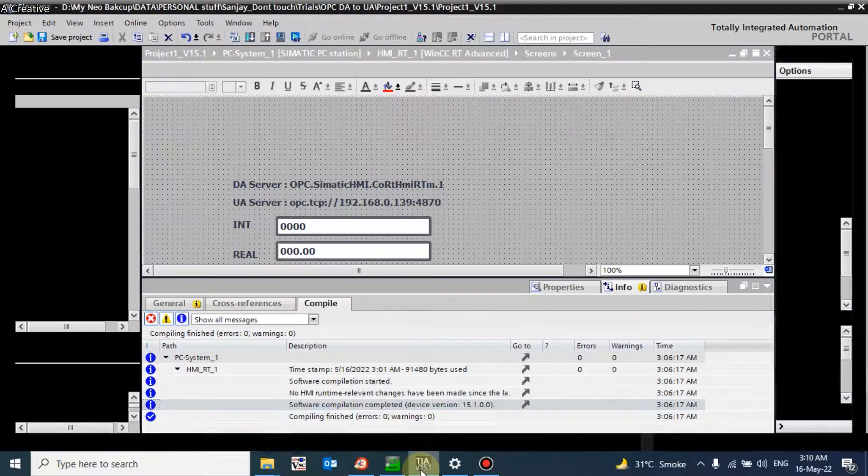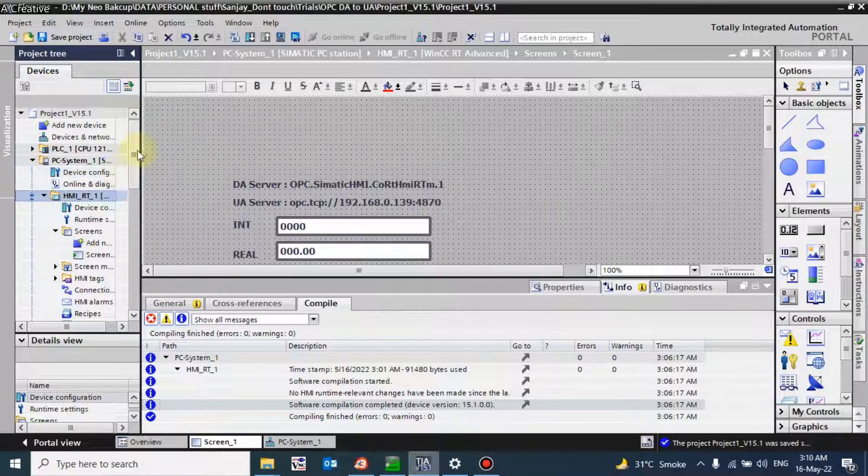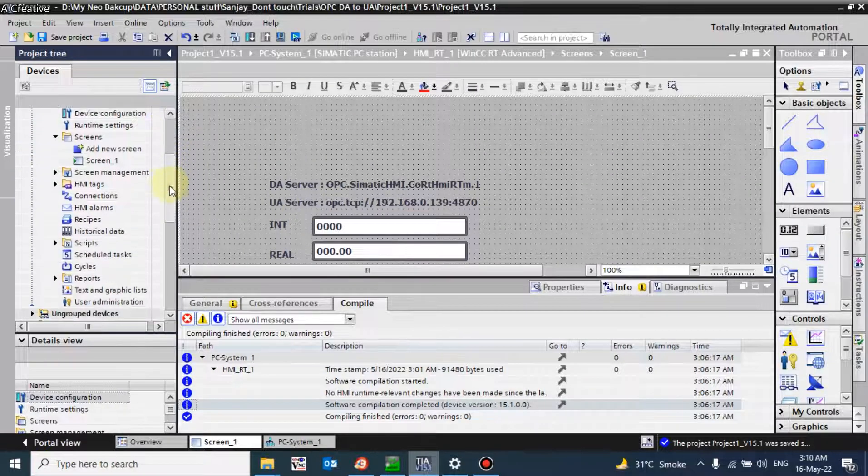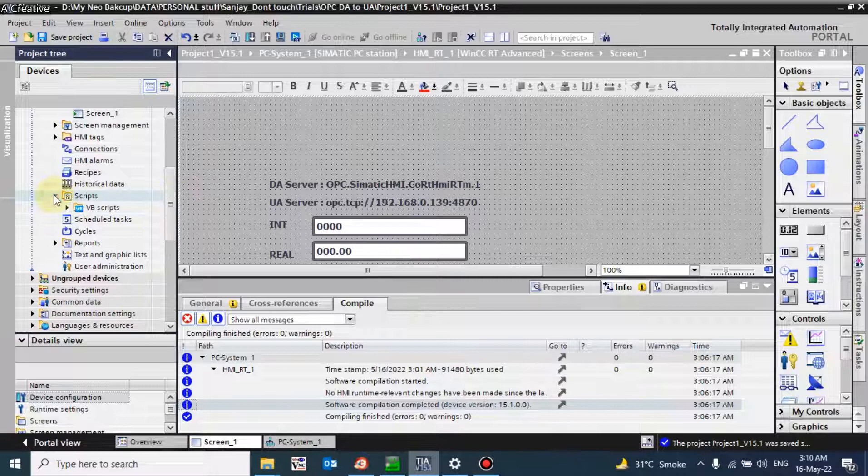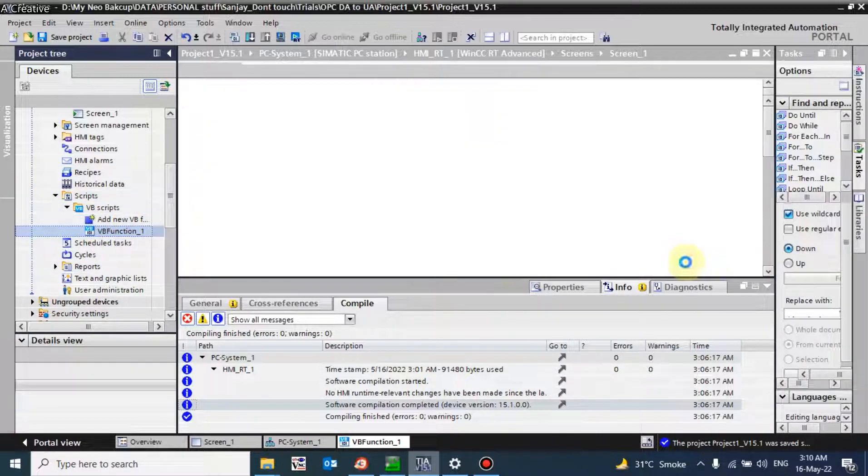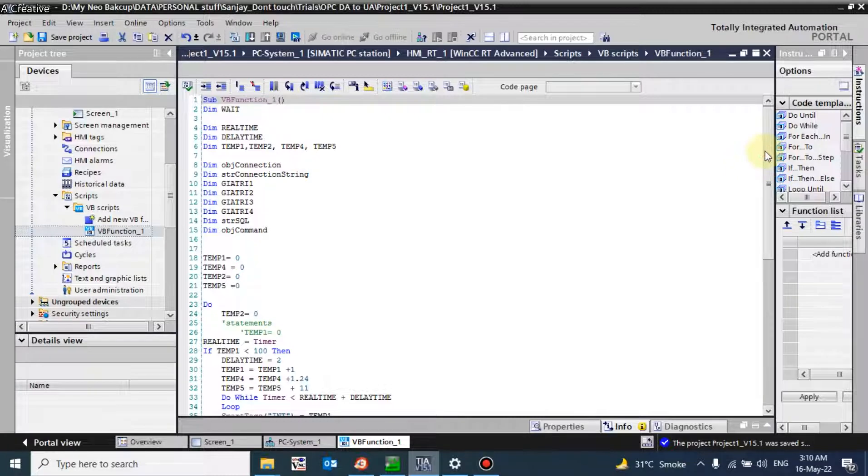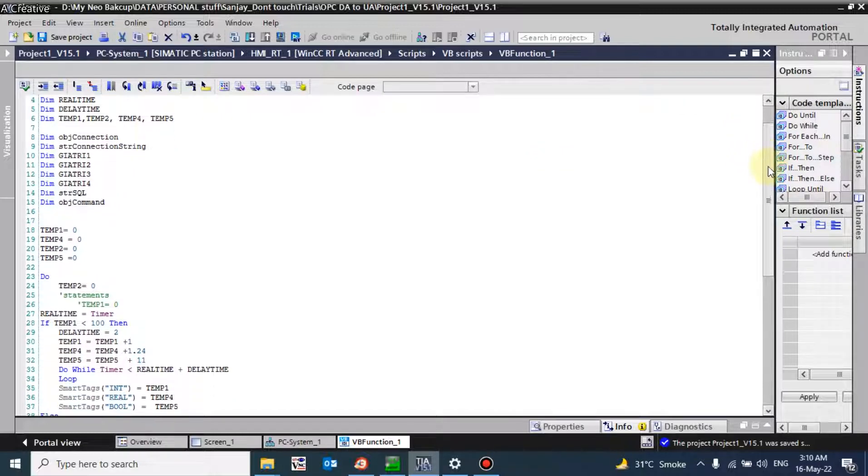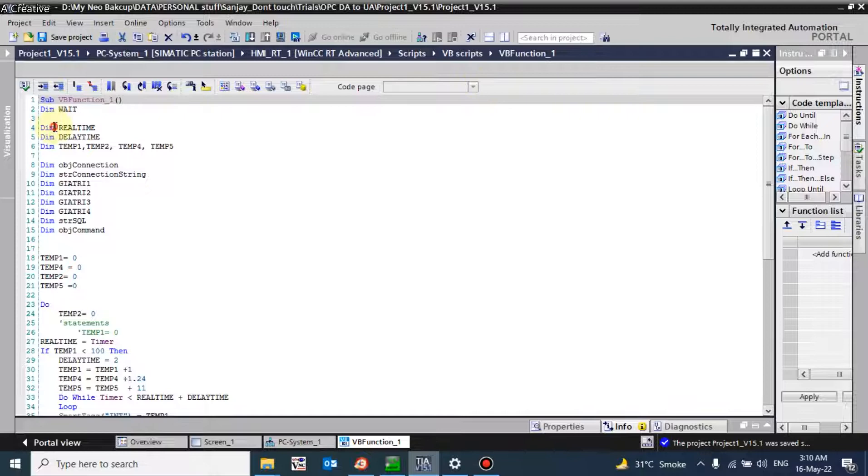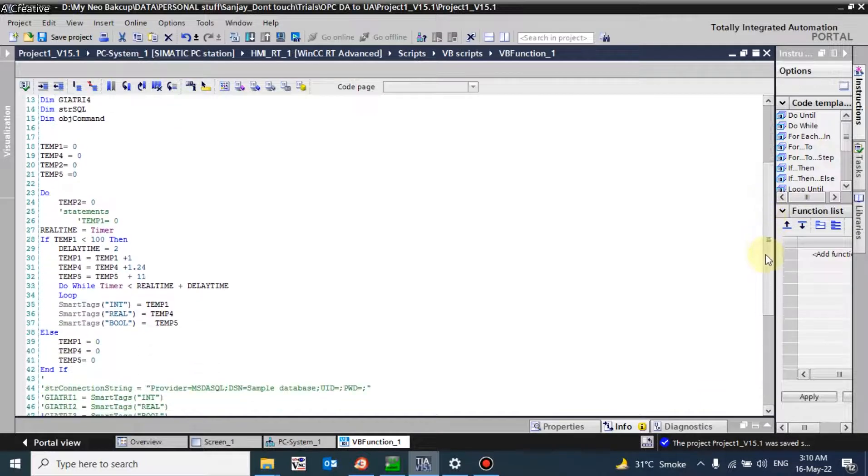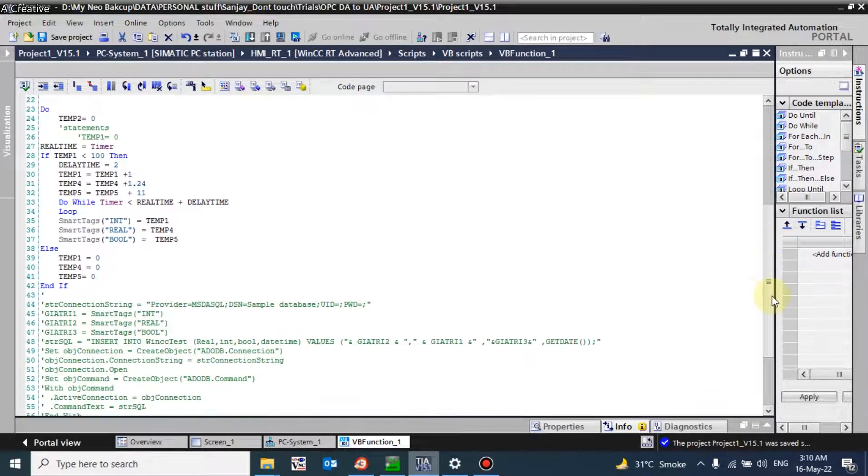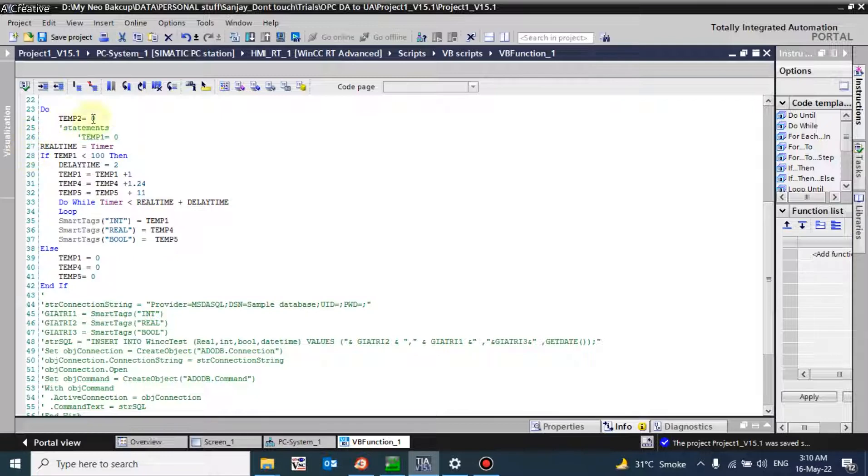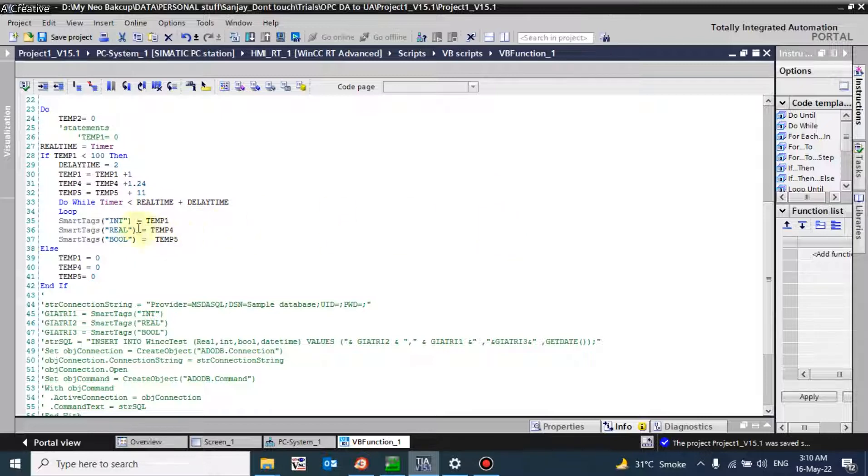First of all, we will create one VBScript to give simulation value for our tags because we have no PLC connected here, so we will create simulation tags. This is the SQL script. We have mentioned the necessary variables which we are going to use here. I have used a do-while loop. This loop will continue executing and will increase three values. I have taken three variables: one is integer, one is real, and one is bool.